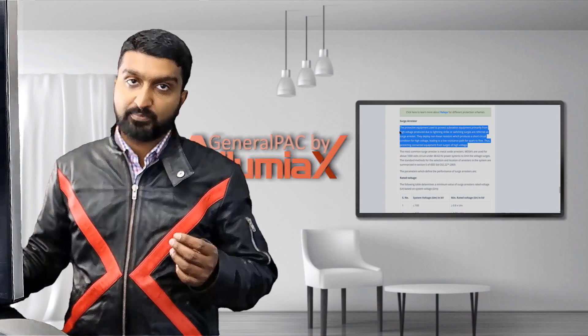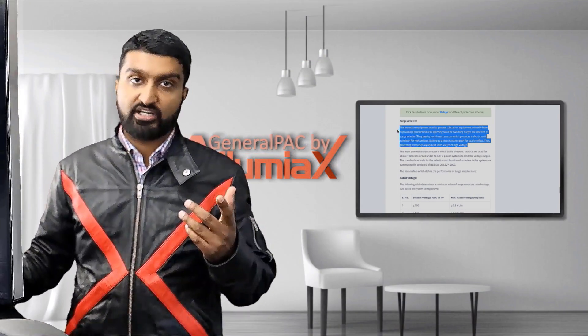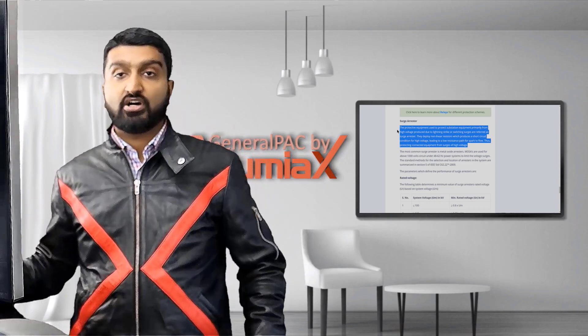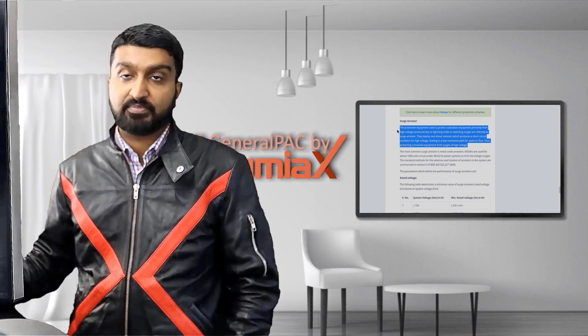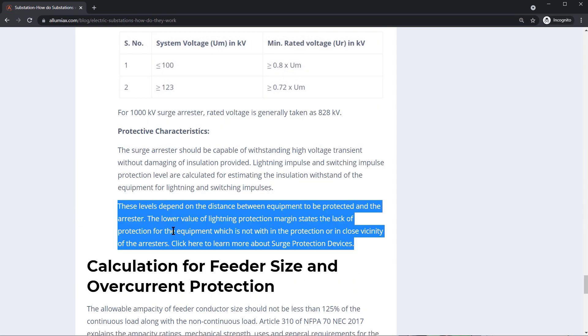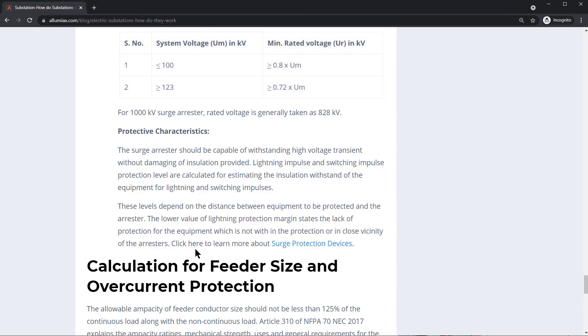Surge arresters are really important for areas where there is a lot of lightning, and are very common in nearly all outdoor substation applications. For systems with voltage under 100 kV, the minimum rated voltage of the arrester should be above 0.8 times UM, to ensure protection of equipment not in close vicinity of the arresters.